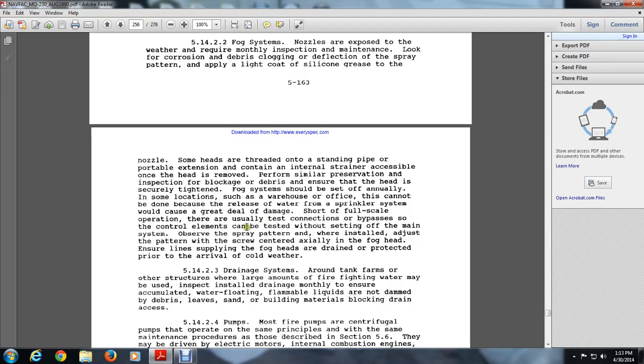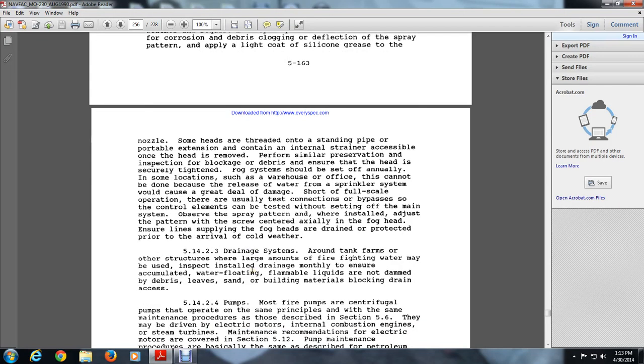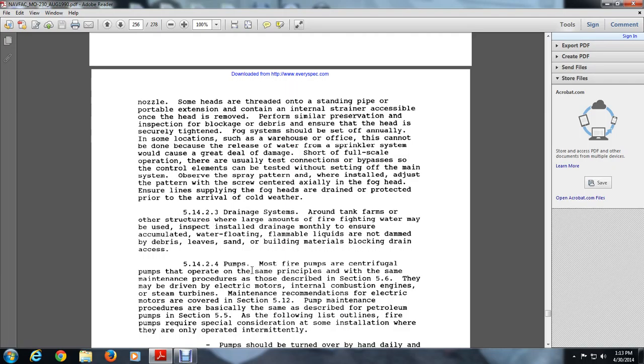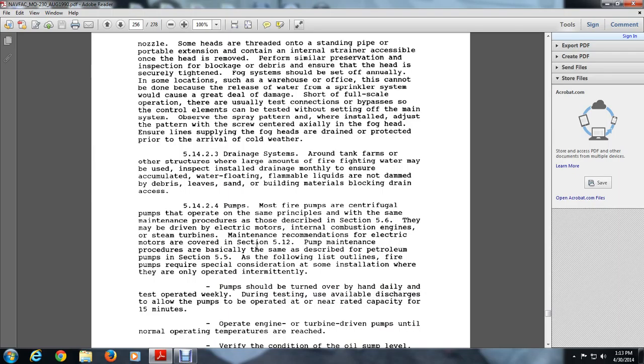5.14.2.4 Pumps. Most fire pumps in the central facility operate on the same principles, with the same maintenance procedures described in section 5.6, and they may be driven by electrical motors, internal combustion engines, and steam turbines with maintenance recommendations. Electrical motors are covered in section 5.12, and pump maintenance procedures are basically the same as described for petroleum pumps in 5.5. The following list outlines fire pumps and required special considerations at some installations where they are operated intermittently.